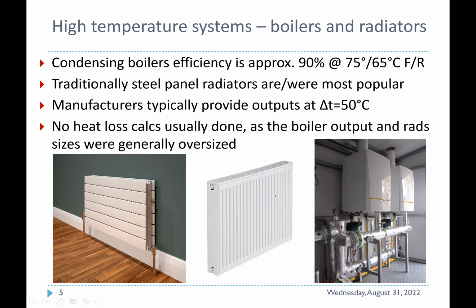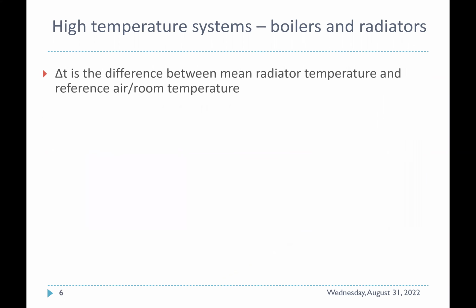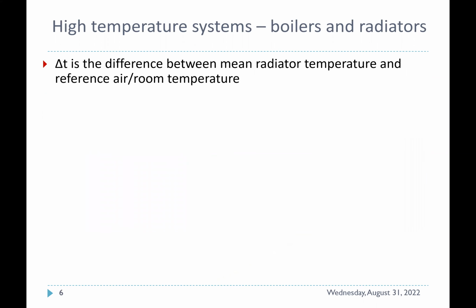Aluminium radiators have also become very popular, but mostly used in conjunction with low temperature systems due to their low water content. Let me explain a little bit and go into more detail on the delta T that is spoken about a lot. The delta T50 is the mean radiator temperature and the difference between that and the air or the room temperature.